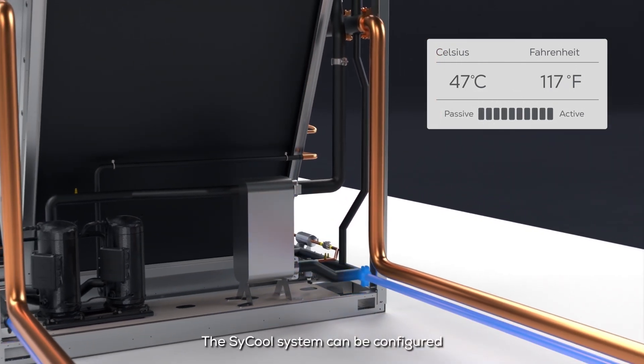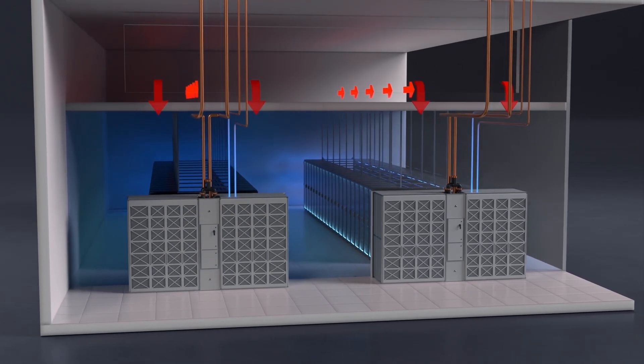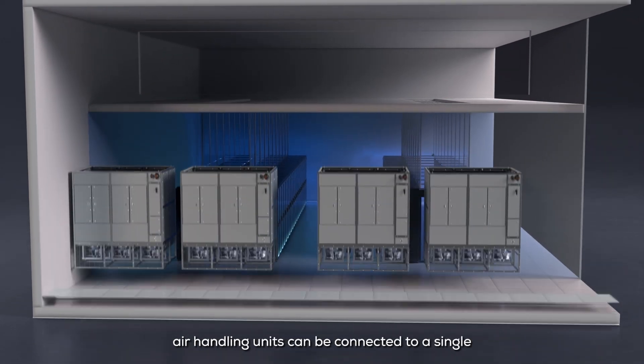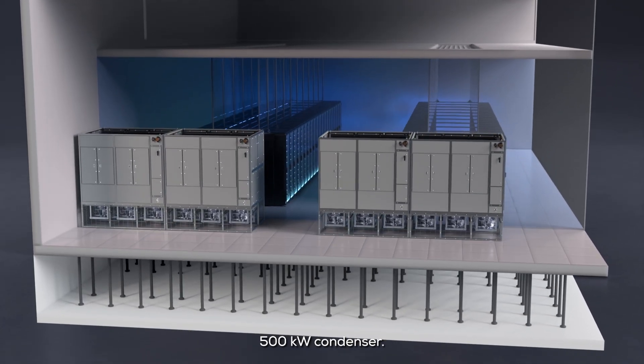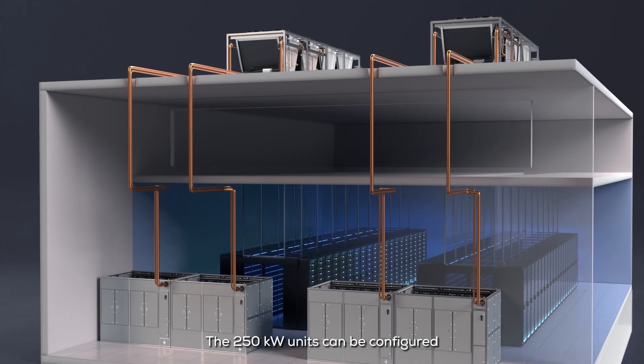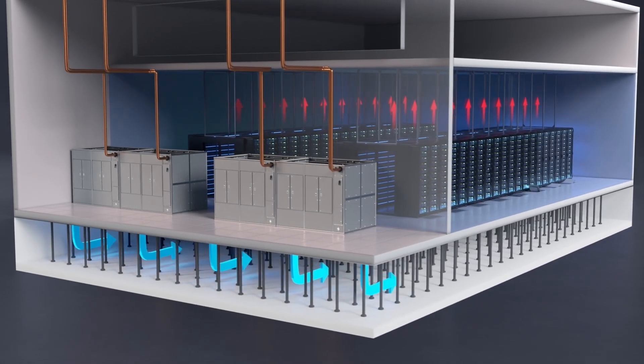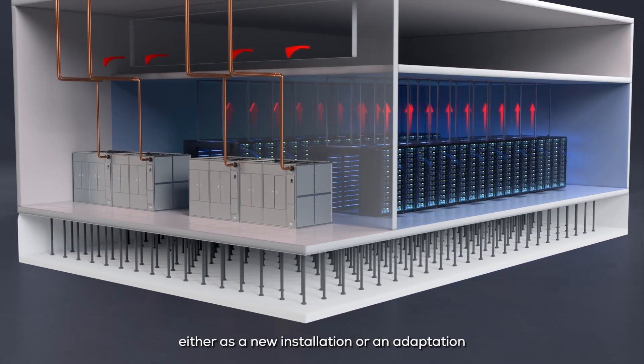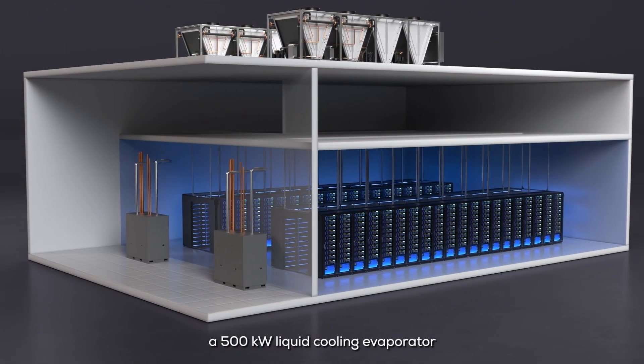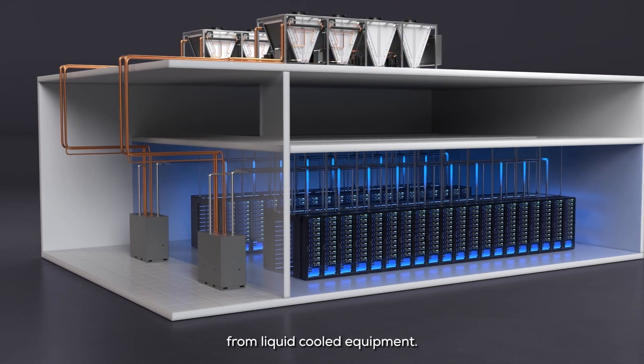The SyCool system can be configured in multiple ways depending on the design of the data center. For example, two separate 250 kW computer room air handling units can be connected to a single 500 kW condenser. The 250 kW units can be configured for flooded room or underfloor air distribution. If liquid cooling is required, either as a new installation or an adaptation from an air-cooled system, a 500 kW liquid cooling evaporator can be provided to remove heat from liquid cooled equipment.